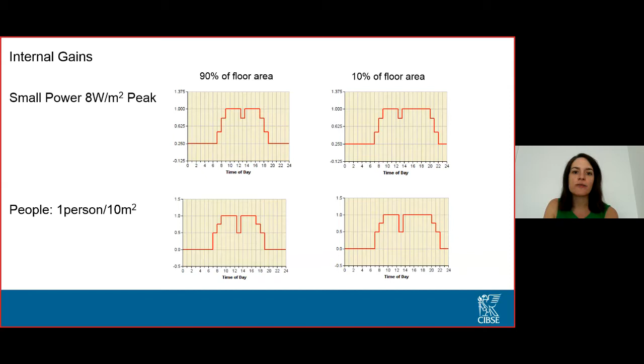The reason behind that: firstly, we're looking to the future, where there's a reduction in screen energy usage, more efficient screens, more use of laptops, and reduced power consumption. We've also factored in diversity within the office - we know that 20-30% of people are not in the office every single day, whether sick or on annual leave. It's by taking this realistic analysis of internal gains that we can really deliver key energy savings.